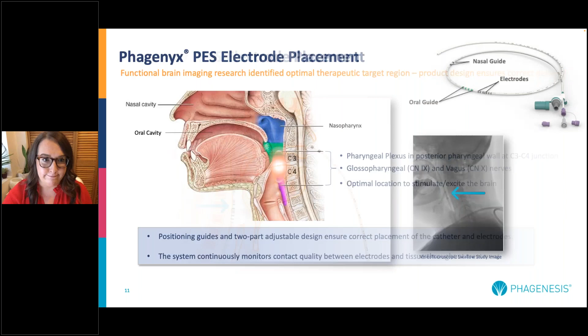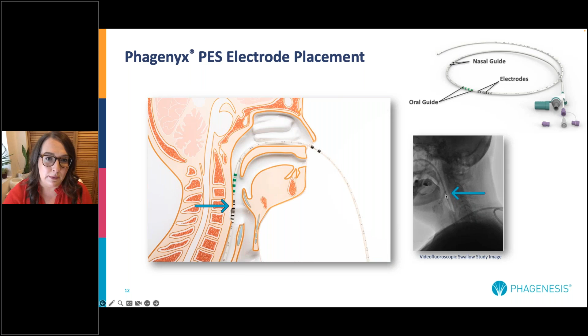And for the clinicians in the audience, the low level energy that's being delivered to the pharyngeal mucosa, we're specifically targeting cranial nerves 9 and 10, those sensory nerve fibers. And as mentioned, it is adjustable to meet various adult anatomies, and it measures electrode contact throughout the duration of treatment. Here's another image of the catheter in place. So we've got our black nasal guides, which are positioned right here outside the nose. We have our green oral guides, which you can see in our model, are right here. And then we have our electrodes, which are the blue arrow. So we have the electrodes positioned right here, and then this is a videofluoroscopic image of the electrodes positioned in a patient.